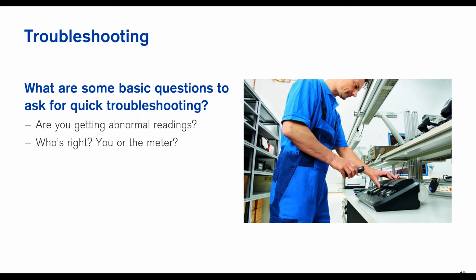If you're using a meter with a Wheatstone bridge sensor or catalytic bead sensor, it has to have an adequate amount of oxygen content. If that oxygen content is thrown off, my meter readings will be too. With low oxygen, readings might read low, because the sensor works by passing gas through plexiglass bulbs, drawing the sample across the exposed bead. The combustible atmosphere interacts with the coating on the bead, causing it to heat up by oxidation, which creates a change in resistance. The meter looks at the difference in resistance and displays that as a reading.